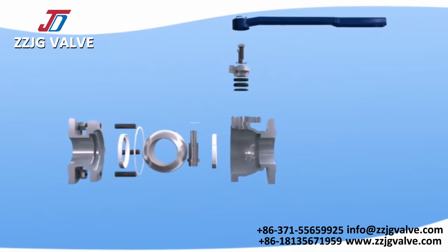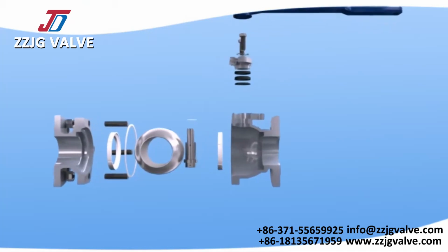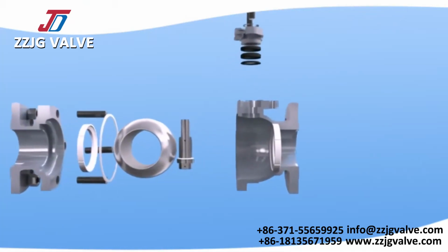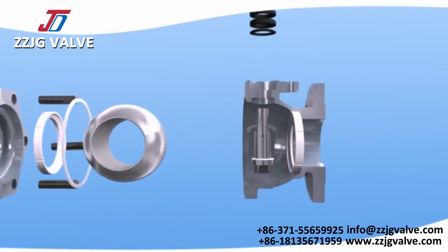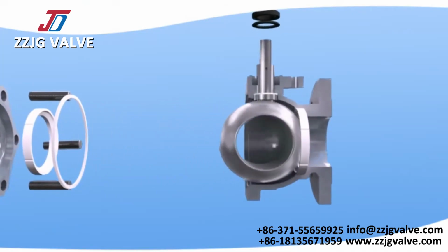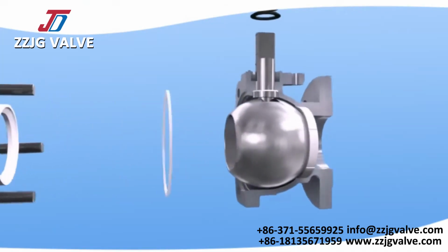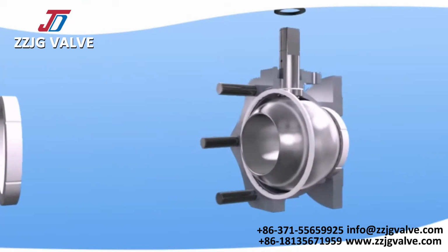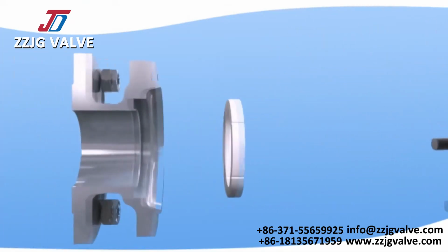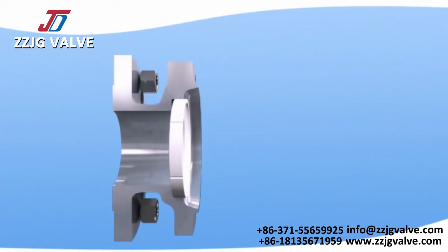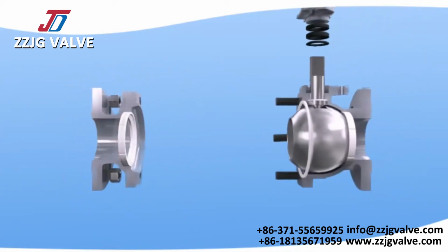pipeline. When the stem turns 90 degrees, the ball hole is perpendicular to the valve channel, making the ball closely pressed into the seat ring on the exit end by medium pressure, which ensures the good sealing of the valve. The advantages of floating ball valves are as follows.